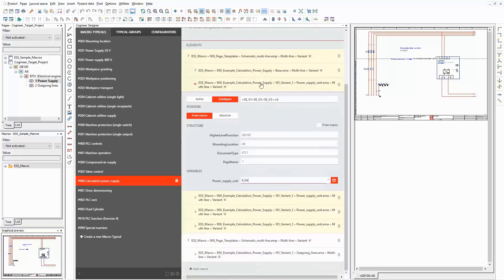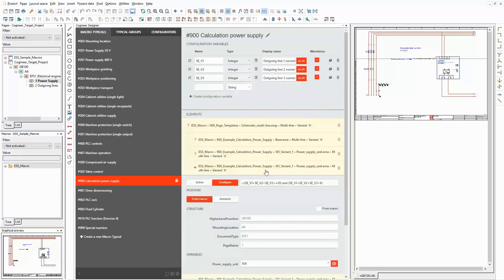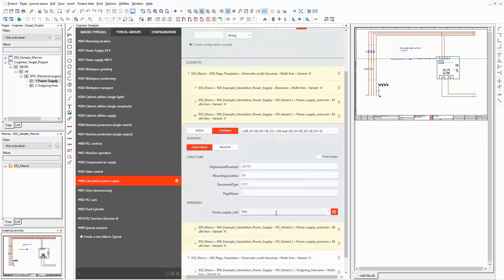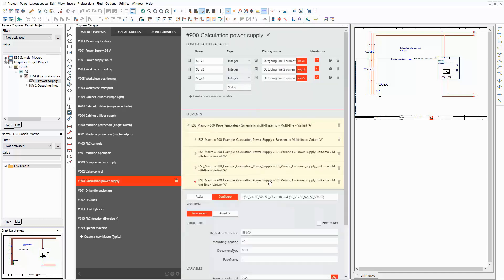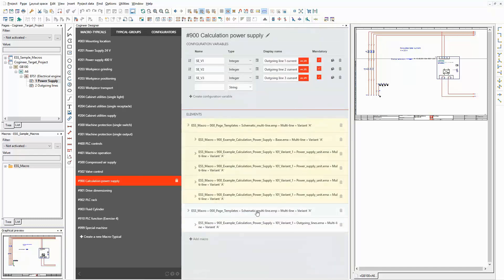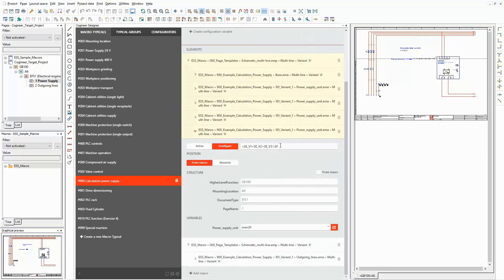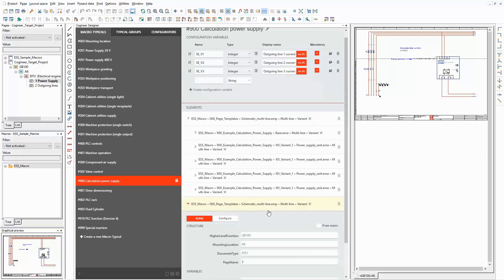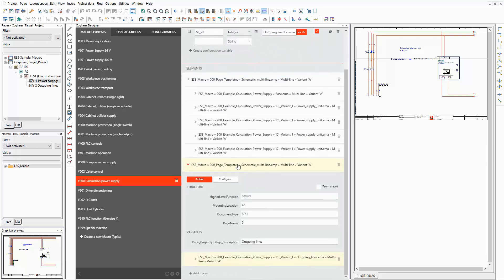The selected value set, 6.5 amperes, is connected to a power supply unit that can handle the current load. The second macro is used if the sum is between 6 and 10. The according power supply unit can handle up to 10 amperes. The third macro is used if the sum is between 10 and 20. The according power supply unit can handle up to 20 amperes. The last macro is used only if the sum is above 20. The according value set contains the same power supply unit as the last one, but the overload is indicated in the schematic. In the second block you can see another empty basic page. The macro for the outgoing lines is placed on it.